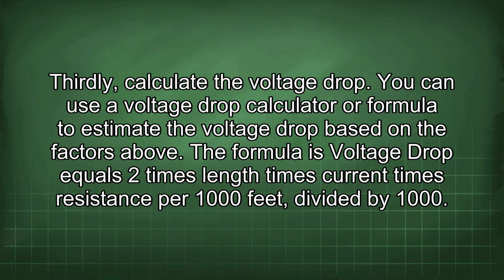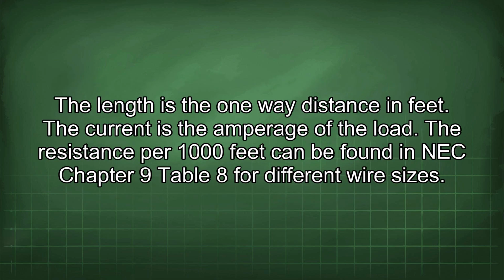You can use a voltage drop calculator or formula to estimate the voltage drop based on the factors above. The formula is voltage drop equals 2 times length times current times resistance per 1000 feet divided by 1000. The length is the one-way distance in feet. The current is the amperage of the load. The resistance per 1000 feet can be found in NEC Chapter 9 Table 8 for different wire sizes.